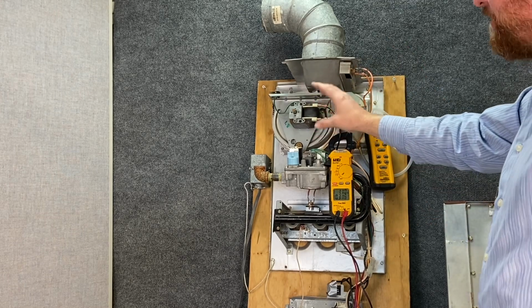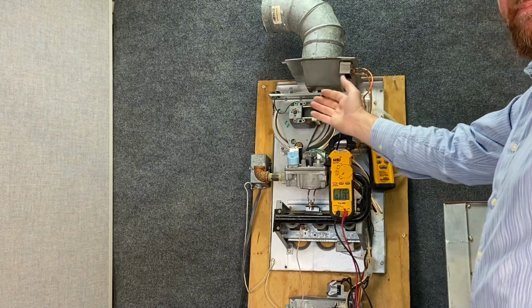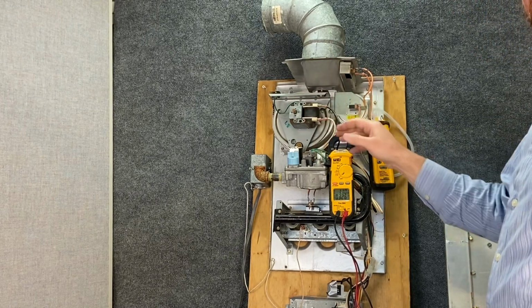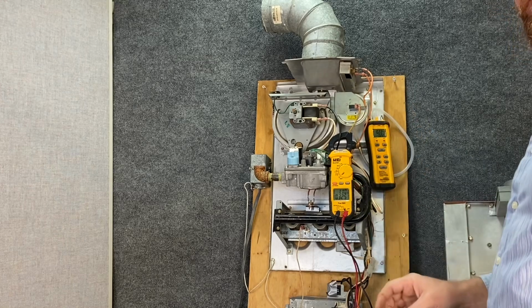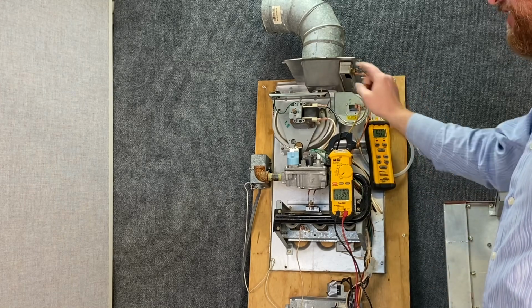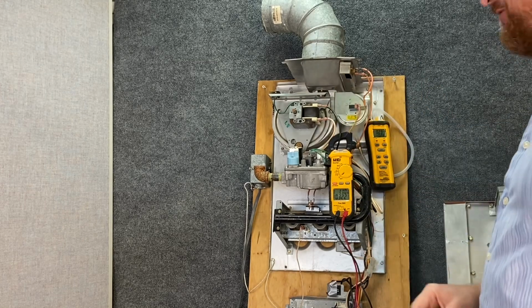My next step would be to shut the system off and then pull this motor out to physically look at the heat exchanger and physically look at the wheel. Now it's worth the risk of checking that gasket material.